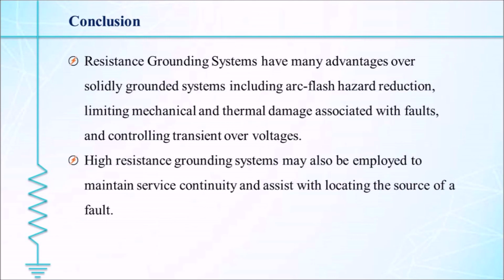Because of heavy fault current, the conductor may get damaged, because protection relays need some minimum time to isolate the power system. For that short period, the NGR limits the sudden flow of fault current from the winding and reduces the exposure to arc faults caused by phase to ground faults and short circuit, and also reduces energy available to the arc flashes. Alternative protective systems like direct earthing of neutral cause serious disadvantages like potentially dangerous overvoltages and damaging circuit fault current with possible arc blast. That is not the case with NGR, and most importantly, it ensures personnel and equipment safety. The system stability is also significantly improved. This is all about the NGR.